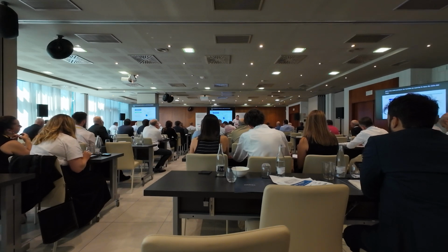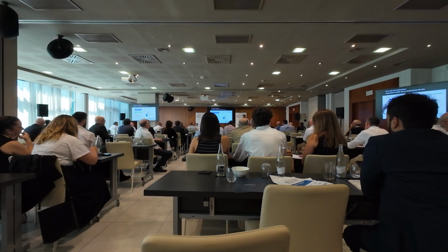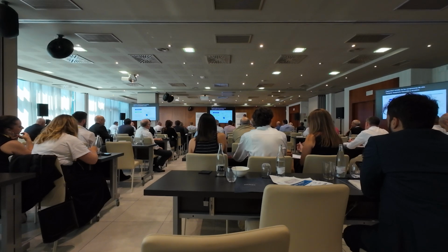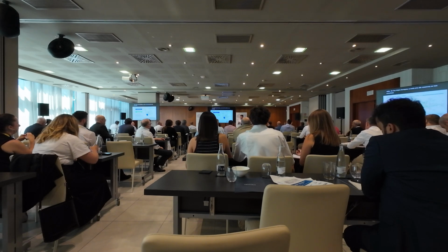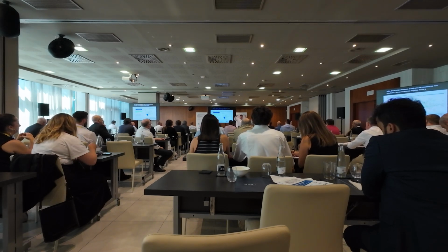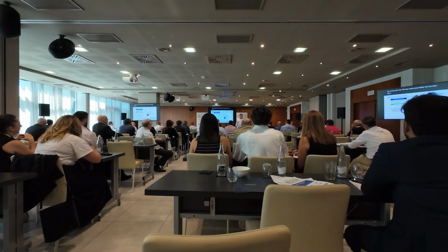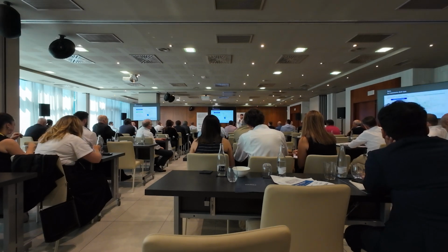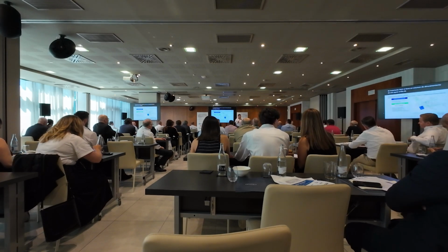In the compressor room, variable capacity of air compressors, wet receiver tanks, and God knows, dryer controls. In the olden days, every one of us was taught to put wet receivers in front of the dryers. Maybe that's the right thing to do, maybe not. I've seen people go to blows over that. There's no reason to talk about that here, but it is important to say if you have a storage volume of air upstream of your dryer and filtration, you cannot size the dryer and filtration solely based on the compressor discharge.